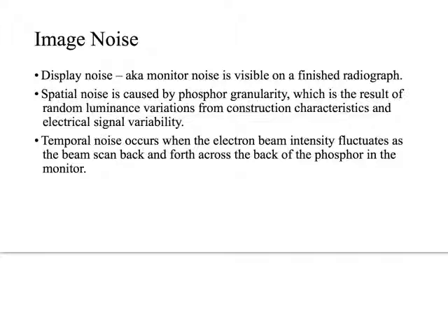So it's important to know, okay, is that monitor noise? Is that noise on the image coming from the monitor? Is it a glitch with the way that my computer radiography reader is working? Where is that noise coming from? And almost every monitor you'll work on at some point will have some kind of problem that comes from just the monitor itself. And the ways that we typically think about this in terms of monitors is spatial noise.